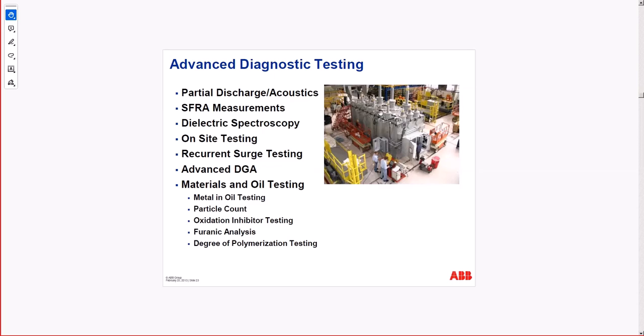The major transformers, like the main output transformers, will have online monitoring. A smaller transformer like 10 MVA or 20 MVA will not. But the main transformers, the MOT and the UST SST, they do have online monitoring for the base gases, not the extra. So it does not calculate or indicate all the gases, but the basic 8 of them.